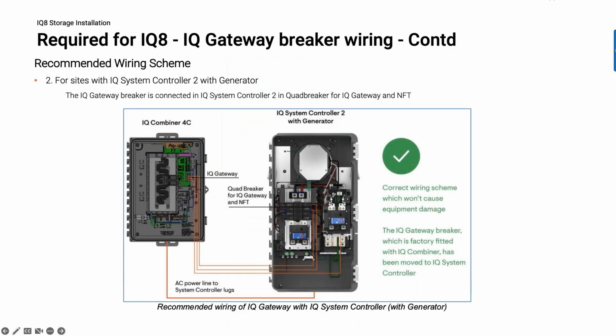And then the other option as well is you can power the IQ gateway from the backup loads panel, because the backup loads panel is connected onto the output of the system controller, right? So if this system controller is feeding a backup loads panel that I'm just drawing here with my arrow, you could potentially feed that gateway from this backup loads panel. And again, it's got the same dynamic. It's actually being powered directly from the common bus here.